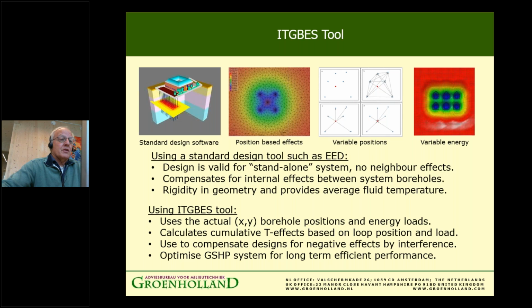But as you can see in the second image at the top, if you compare this to a dice with the number 5, the central borehole has effects from all sides, while the boreholes on the perimeter have less temperature effect than the central one. In the third image, with variable positions, you can see a borehole, the red one in the middle, influenced by other boreholes, not always in a fixed geometry, so it's less rigid, with variable positions and variable energy rates on each borehole. Say each borehole, or each point, represents boreholes for a certain house. There's a difference in distance, so there will be different relationships between the boreholes.